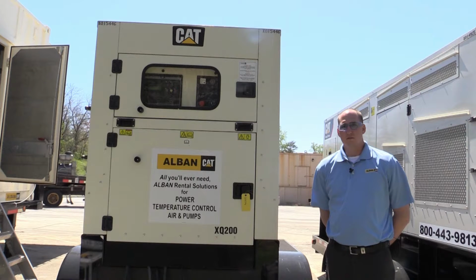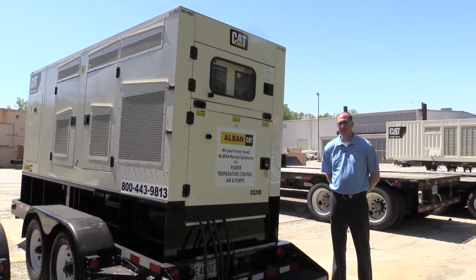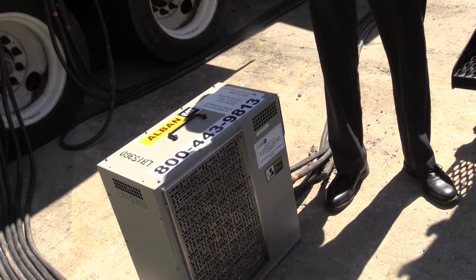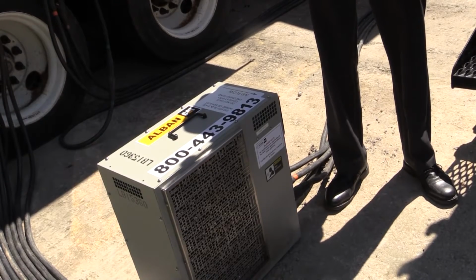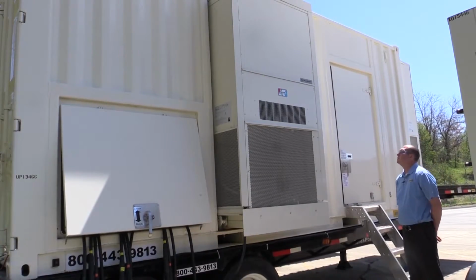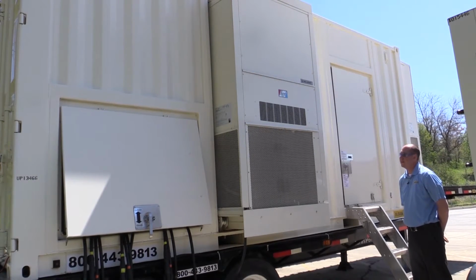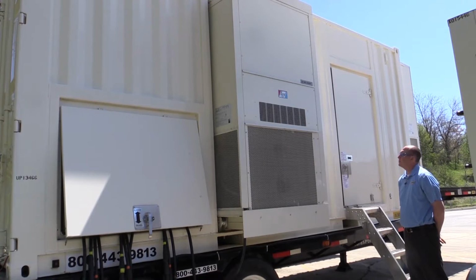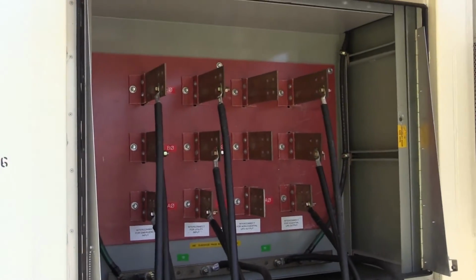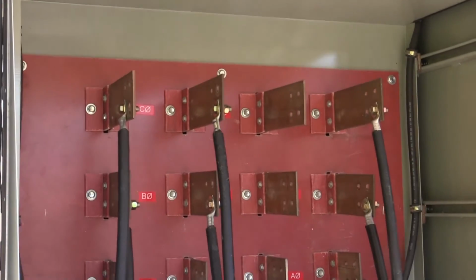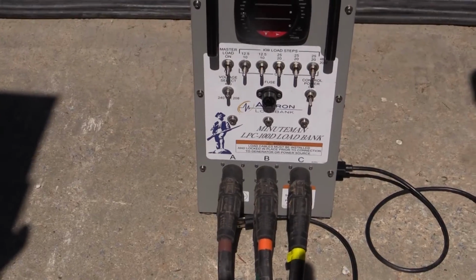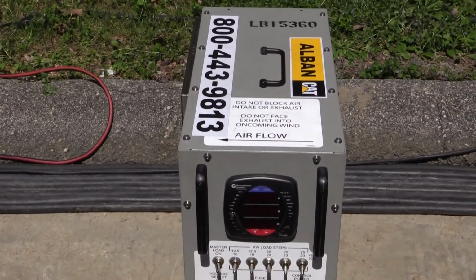This is our utility generator. It's a 200 kW rental package from Alban CAT. This is going to send power to our utility side of our UPS. This is our 200 kW generator that we will use as our emergency backup. This is our 100 kW load bank, which will signify our essential load. This is the 600 kVA self-contained Alban CAT Rental UPS. It is a flywheel type UPS. Take a look at the bus bar connections on the 600 kVA. As you can see, we're attached at the UPS utility input, UPS emergency input, and UPS essential load output.